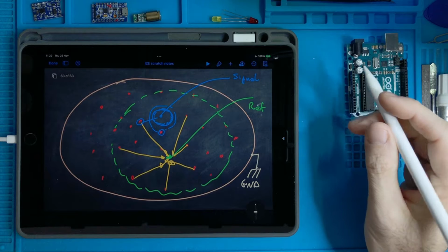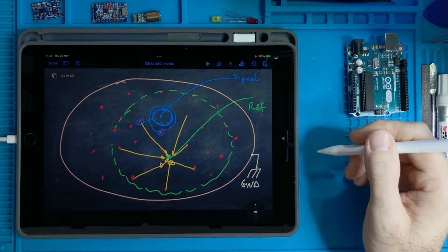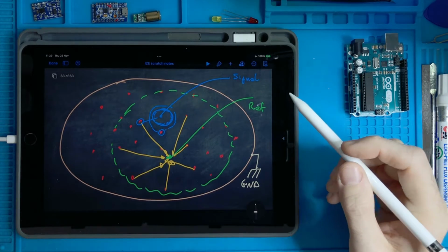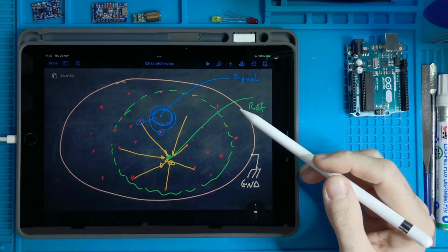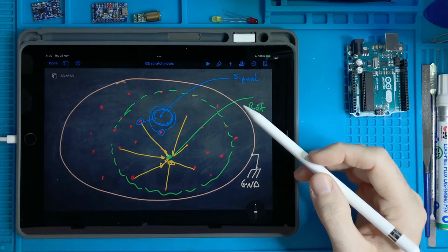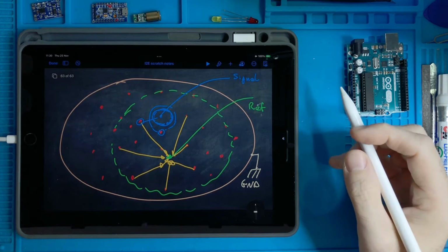fundamental points for the recordings in electrophysiology. Sometimes people have the tendency of connecting the reference to ground because they see noisy signals, and then they say, okay, if I connect this to a good ground point, then I don't see the noise.